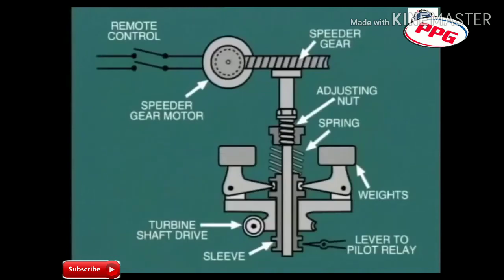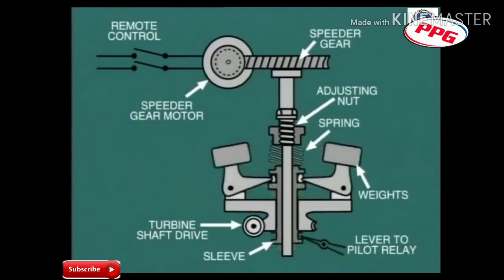Now, let's take a closer look at the governor itself. This mechanical-type centrifugal governor is driven directly from the turbine shaft through a gear drive. As speed increases, the weights fly outward due to centrifugal force and lift the sleeve against the compression spring.